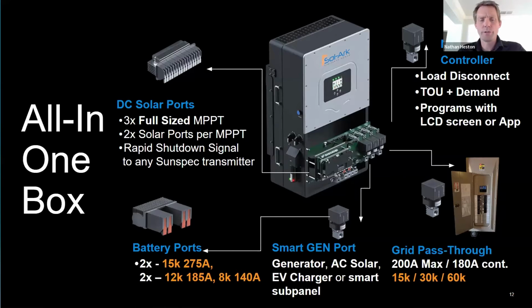So John, I have a question on that. When you are landing the grid, you can either come through fuses or a service entrance rated breaker. And I've heard that you recommend coming through even a bypass switch, potentially a manual bypass switch. What's your preferred method for landing from the grid on the 15K?